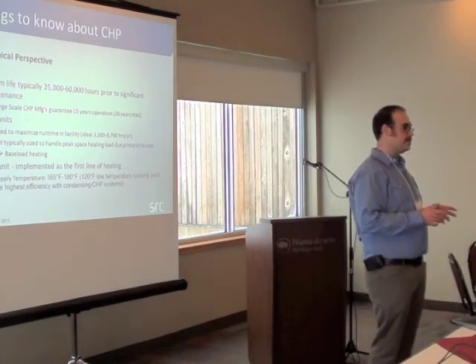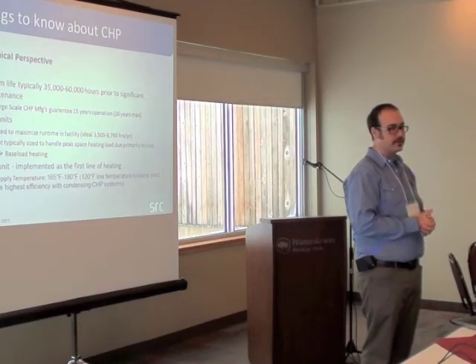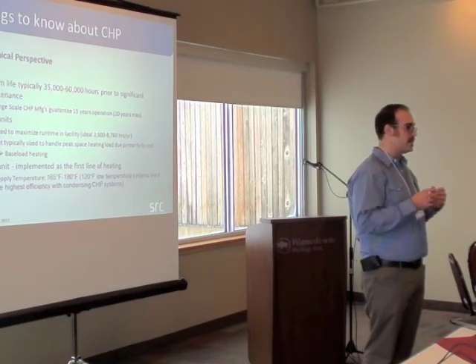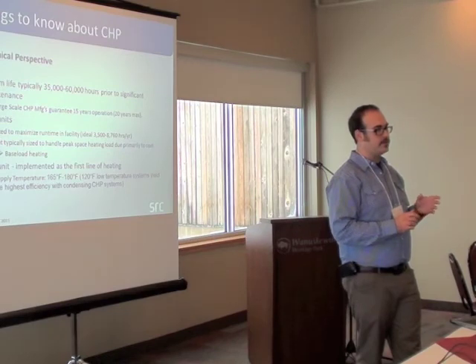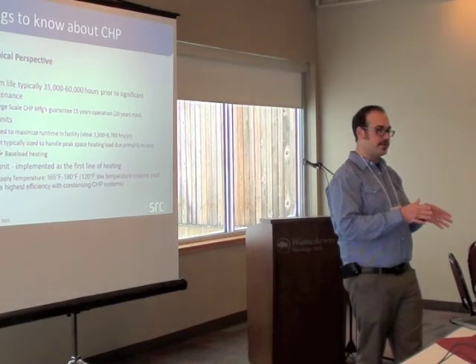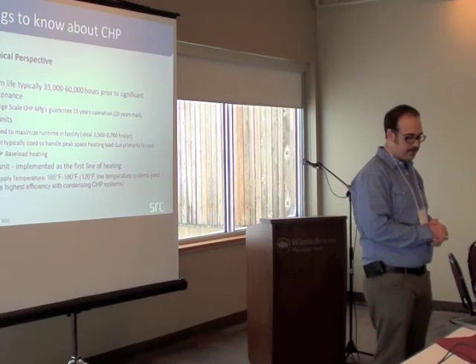From a mechanical perspective, when you're installing or thinking about CHP, some of the important things: system life is typically 35 to 60,000 hours prior to having to do a complete rebuild on the engine or the system. Some of the larger scale CHP manufacturers have 15 to 20 year guarantees, so that gives you an idea of when the system would have to be replaced or overhauled. The system's sized to maximize runtime, so if you needed 100,000 BTUs worth of heating in your building, you wouldn't put in a 100,000 BTU CHP plant. You would put in something smaller that can handle the base load, because you want that system running as many hours in the year as possible to maximize the economic benefits.